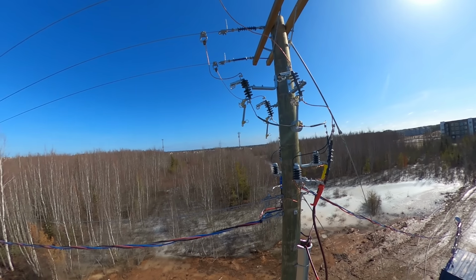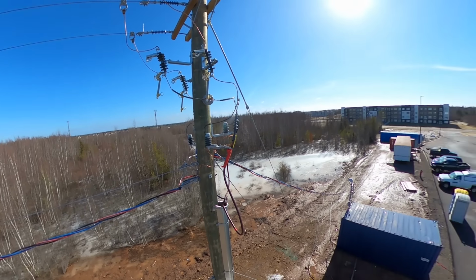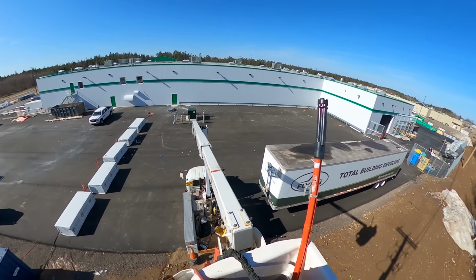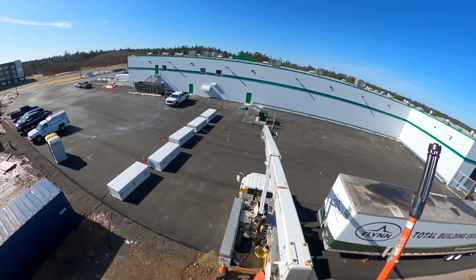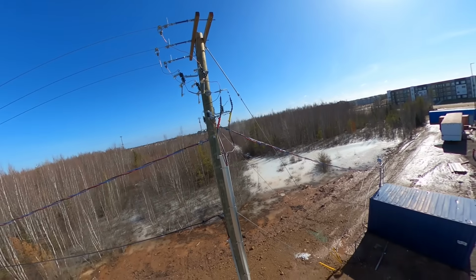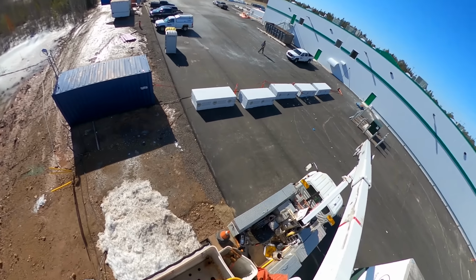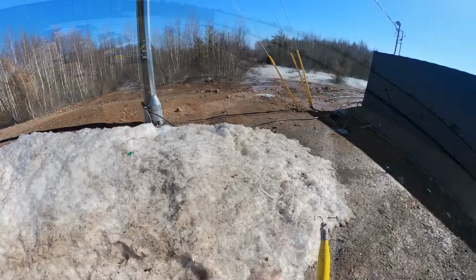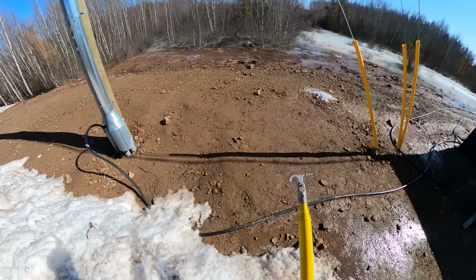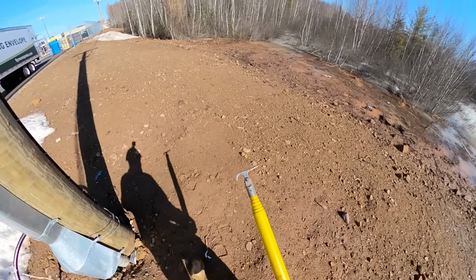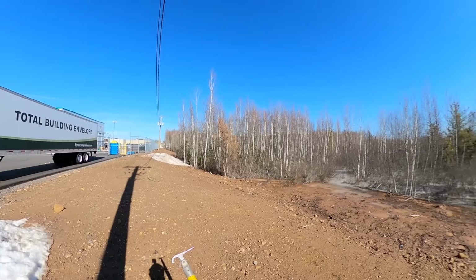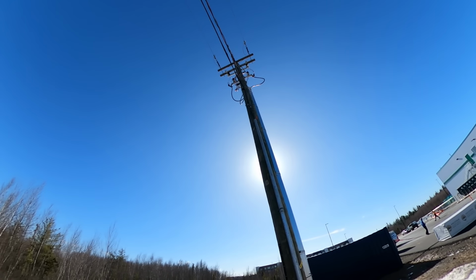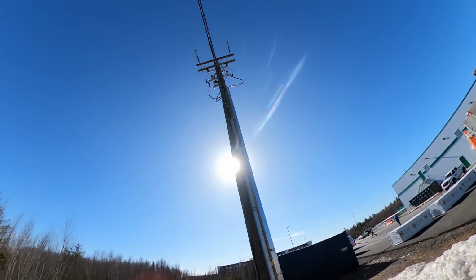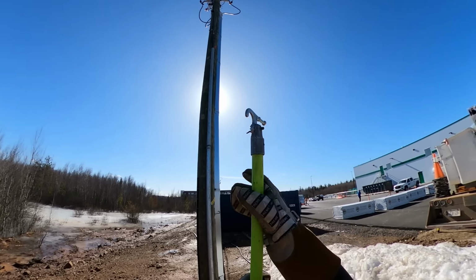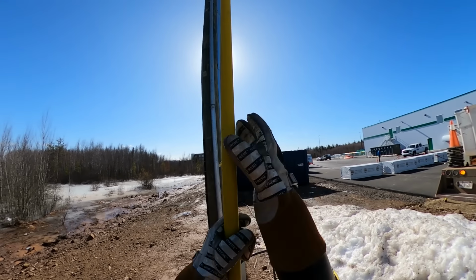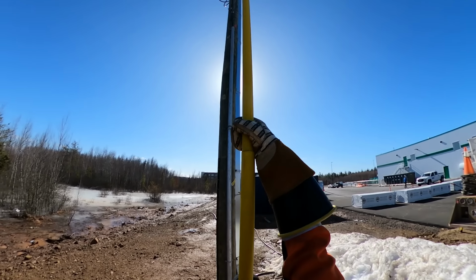That being said, if you ever put those on by hand during construction, you don't want to put a screwdriver and over tighten them either. So we're going to close this from the ground. We're definitely allowed to close it from the bucket if we choose to do so, but if I can close these switches from 30 feet away as opposed to 10 or 12 feet away, definitely going to take that option. I've had enough cutouts blow in my face over the years. Much rather close them from the ground.